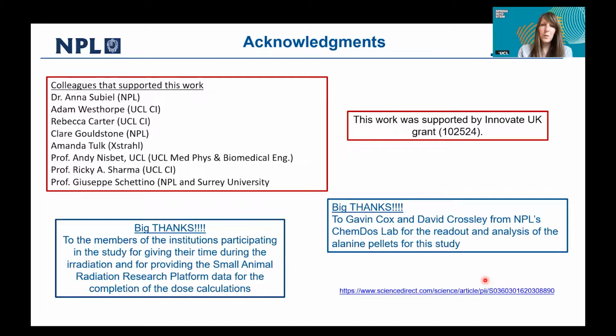Is it possible to use other types of detectors in this kind of end-to-end test? It is possible in a way, for instance when determining dose in more reference-like conditions where there are no collimators or gantries moving around. Yes, you could use ionization chambers, but these small animal irradiators are very contained, very enclosed, so it's difficult to have a cable when the rest of the device will be moving. So alanine offers the possibility of a cable-less detector. In the future, we are trying to introduce detectors that could be read out instantaneously, like the small scintillator I mentioned at the end. But the challenge will be exactly that: how to place the readout cables on the device so that they don't interfere with its movement.